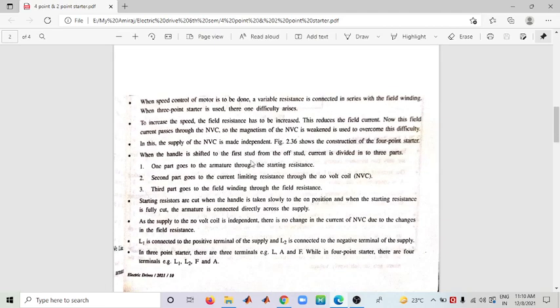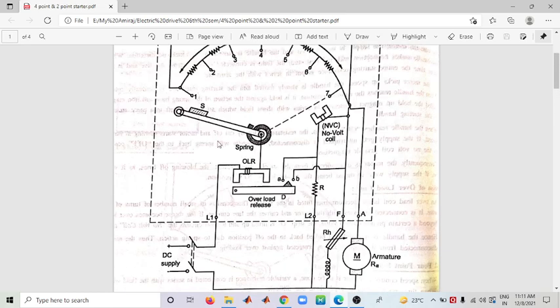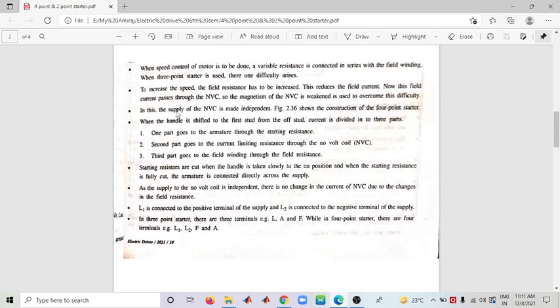The starting resistance is cut as the handle is moved slowly from one position to the next. As the handle moves slowly — from position 1, 2, 3, up to 7 — the starting resistance is cut one by one. When the starting resistance is fully cut, the armature is connected directly across the supply.